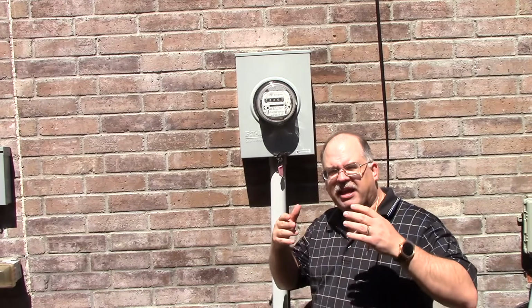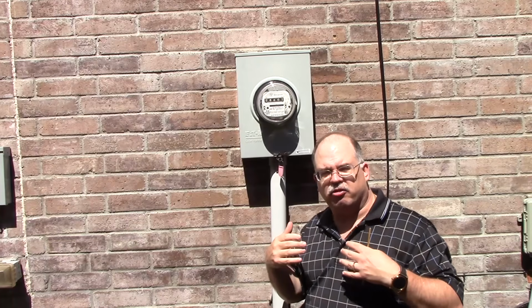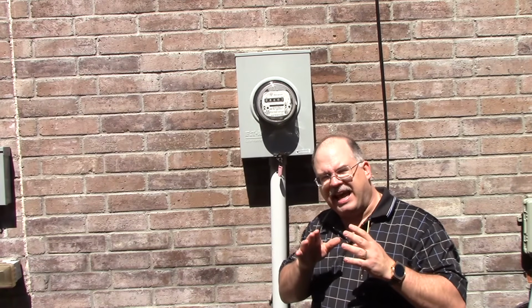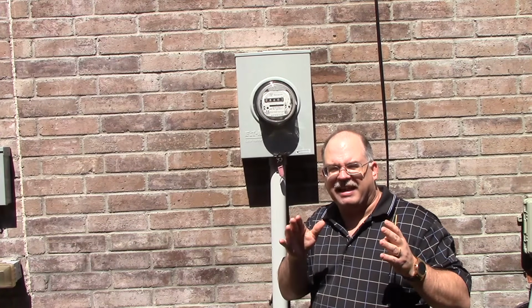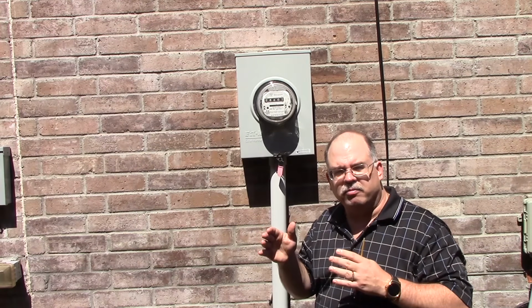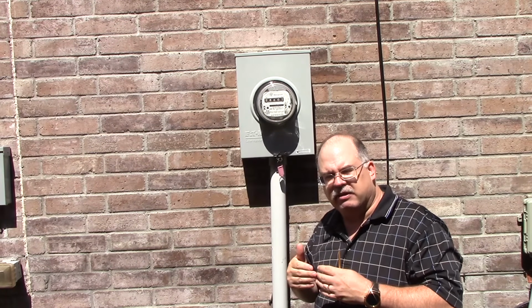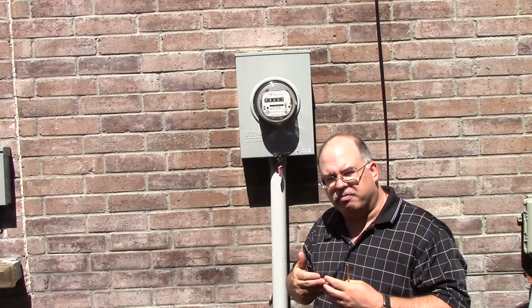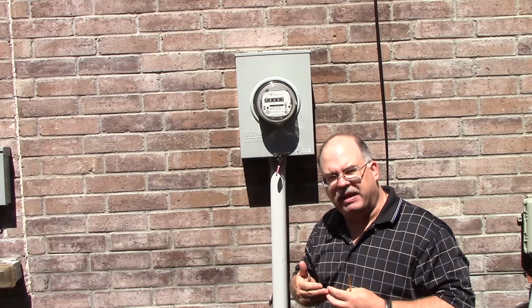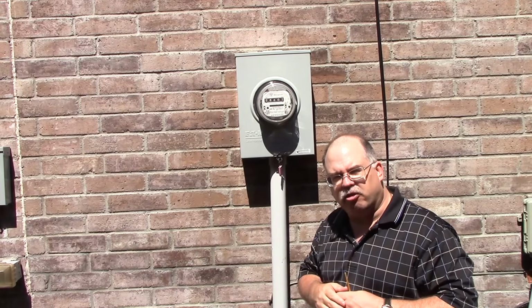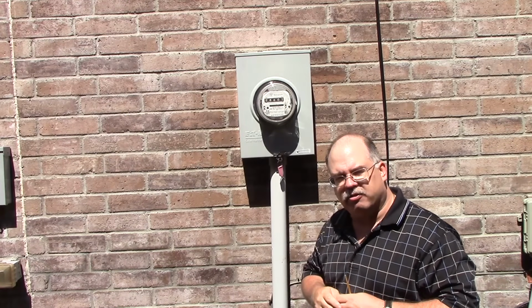Now we know that we have a Ufer ground here, or a concrete encased electrode. And a 4 gauge was run to that. And that's all the code requires for sizing for that concrete encased electrode. They didn't really need ground rods, but they added them in this house. So we're going to look for it and see how many they have and talk a little bit about the grounding electrodes when it comes to ground rods.